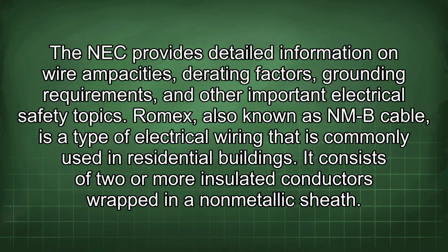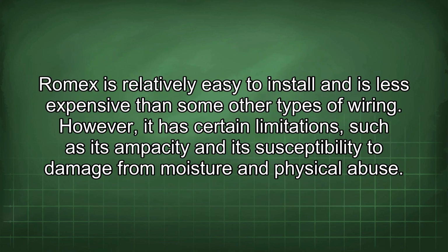Romex, also known as NMB cable, is a type of electrical wiring that is commonly used in residential buildings. It consists of 2 or more insulated conductors wrapped in a non-metallic sheath. Romex is relatively easy to install and is less expensive than some other types of wiring. However, it has certain limitations, such as its ampacity and its susceptibility to damage from moisture and physical abuse.